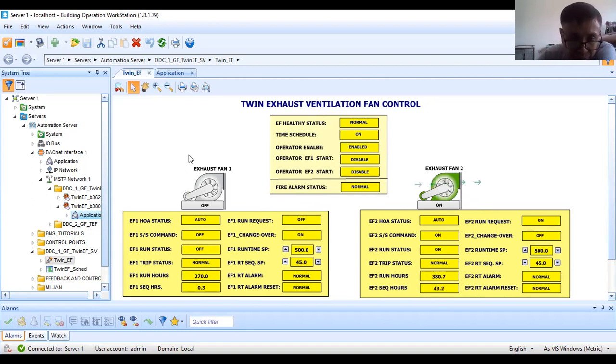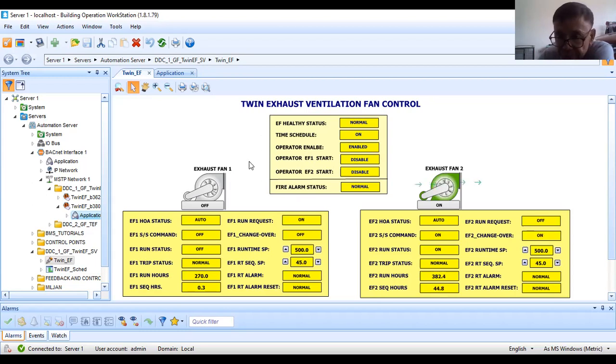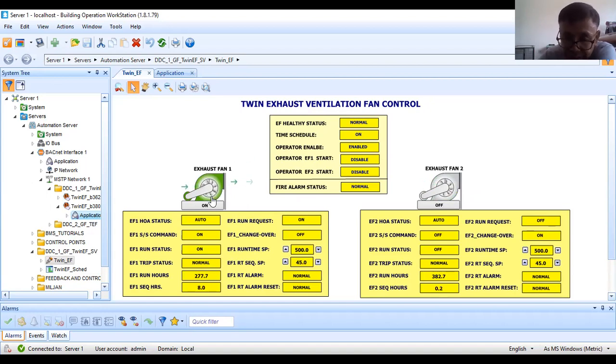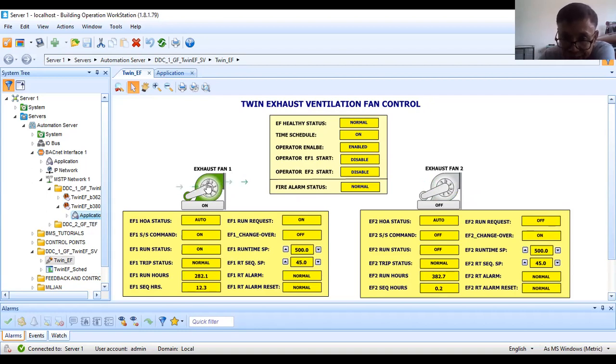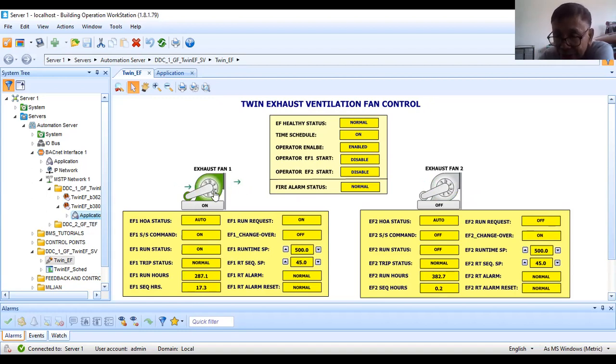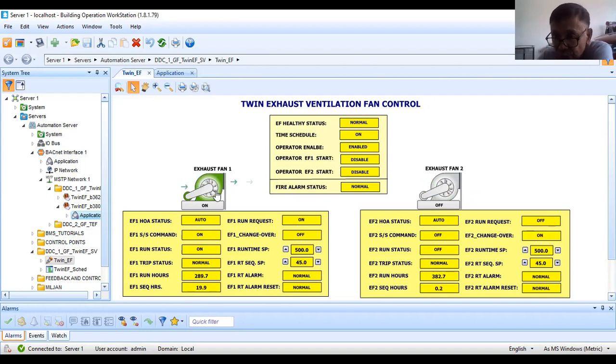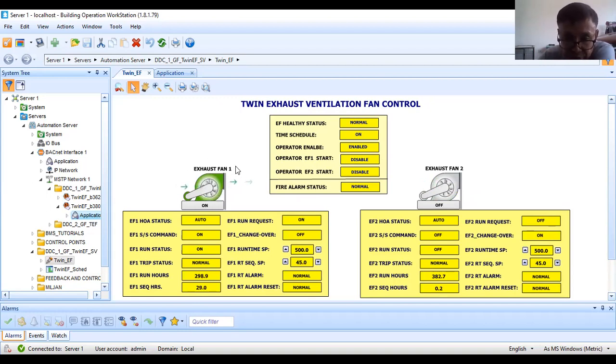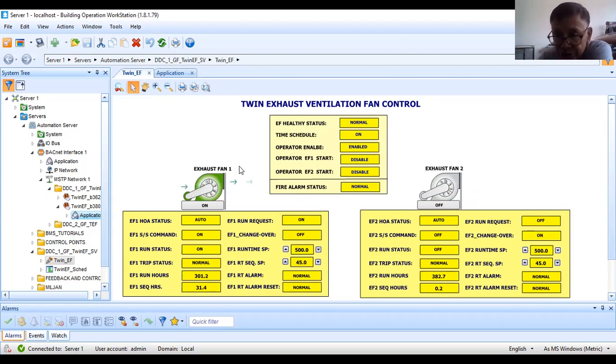We will put here the DPS or differential pressure switch that is sensing the airflow. The purpose is because maybe the motor is working but the belt is broken. Your fan will not rotate, or the belt is cracked. Then the fan will not rotate at 100% RPM. It will not deliver or suck the air from the area. That is one purpose of differential pressure switch. I will include it in the next tutorial.